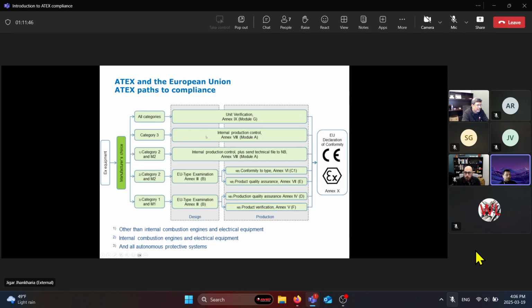It says category 3 here, internal production control. So this is a document that's available online, and I'll try to share that with you, which is pretty much just saying this is why you don't need a quality assurance notification audit for this equipment, because it is classified as category 3. But as you can see, for category 2 and category 1, there is a requirement for product quality assurance as per the annex. And that's basically the QAR, QAN for IECEx and ATEX.